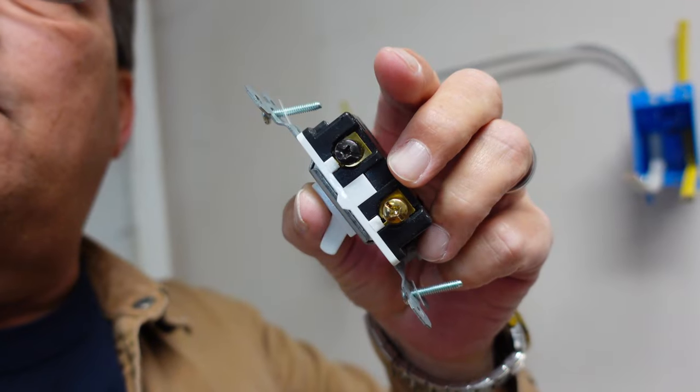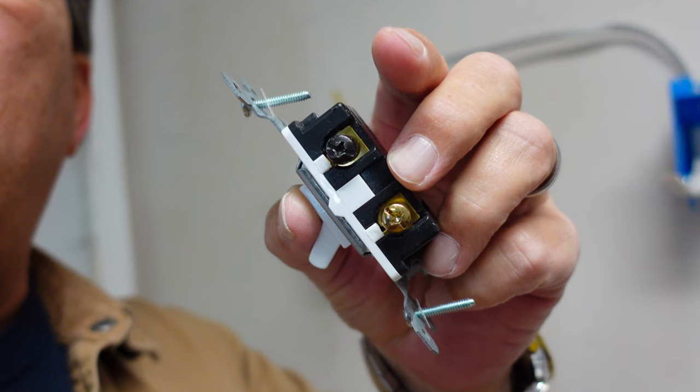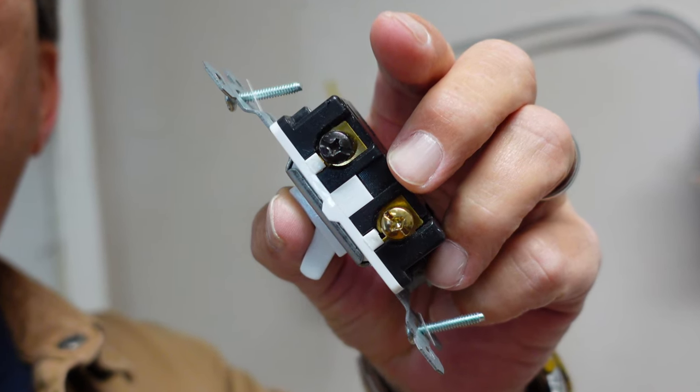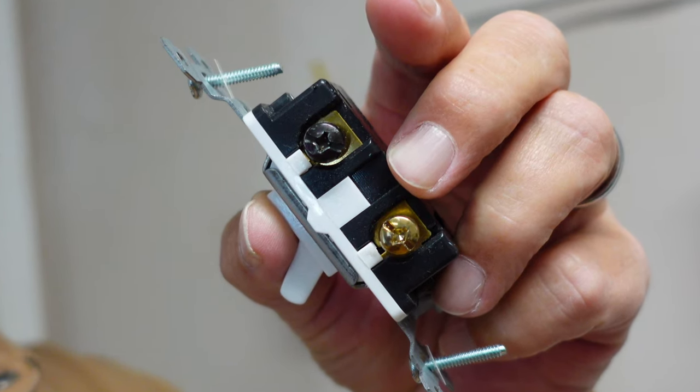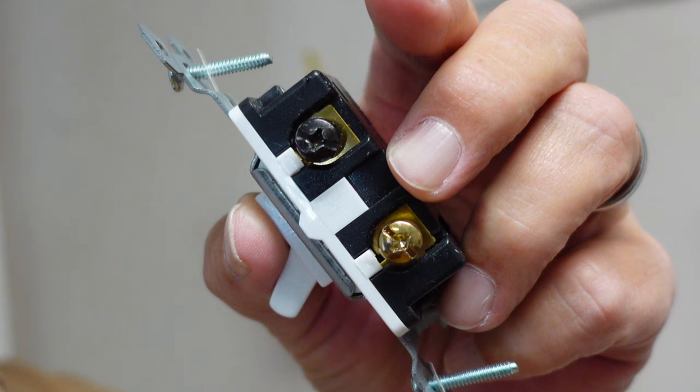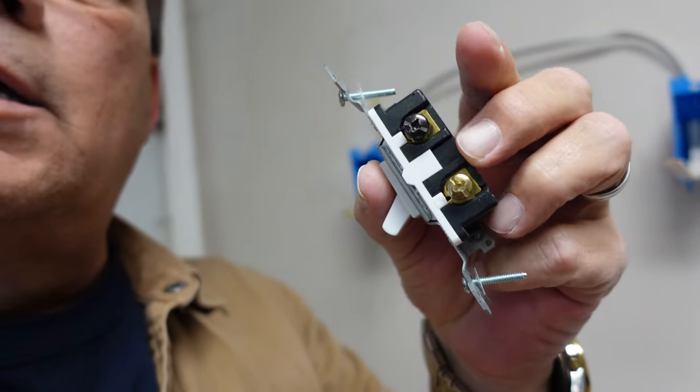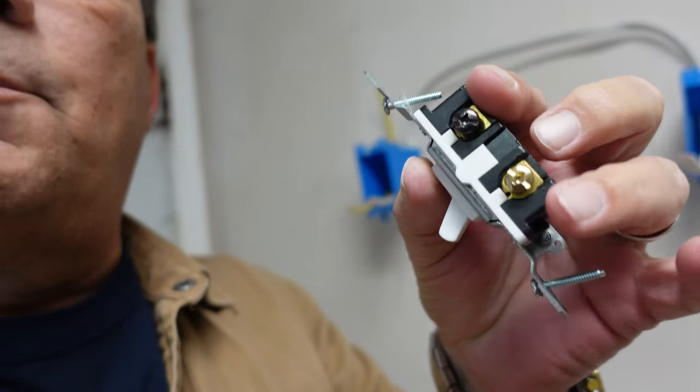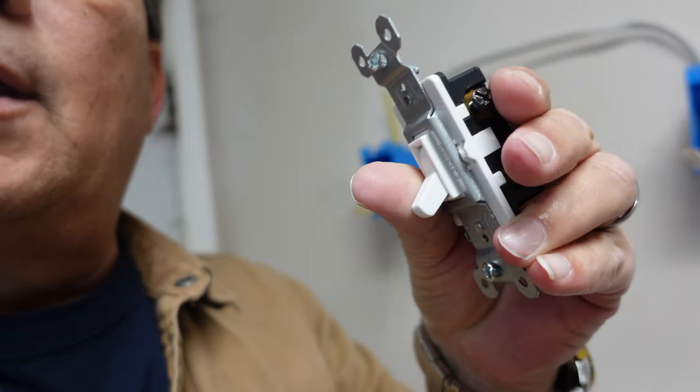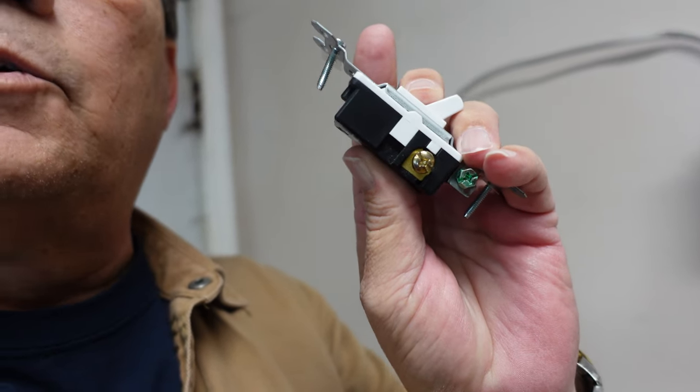Now I'm going to pull a switch here for you. This is the switch. You can see on this switch, this black terminal up here, that's going to be your common leg. That's what your power is going to go on. Power going to the light or power coming from the breaker, whatever the power source is, that's going to go to your common on the switch. The brass screw here at the bottom, and then also the brass screw on the other side, those are your travelers.